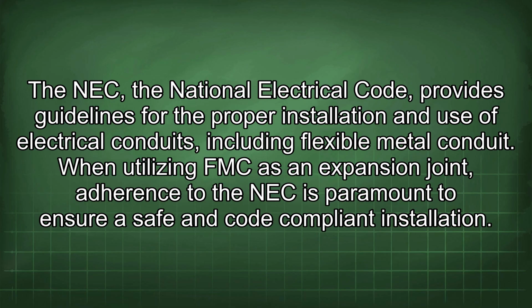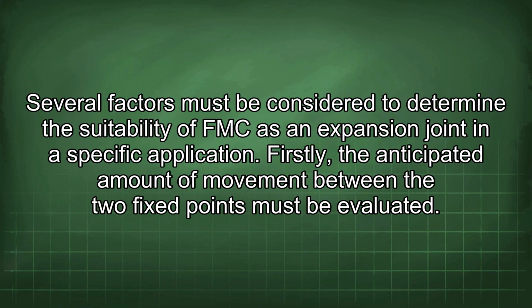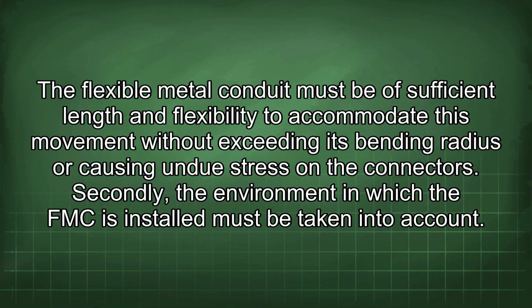The NEC, the National Electrical Code, provides guidelines for the proper installation and use of electrical conduits, including flexible metal conduit. When utilizing FMC as an expansion joint, adherence to the NEC is paramount to ensure a safe and code-compliant installation. Several factors must be considered to determine the suitability of FMC as an expansion joint in a specific application. Firstly, the anticipated amount of movement between the two fixed points must be evaluated. The flexible metal conduit must be of sufficient length and flexibility to accommodate this movement without exceeding its bending radius or causing undue stress on the connectors.